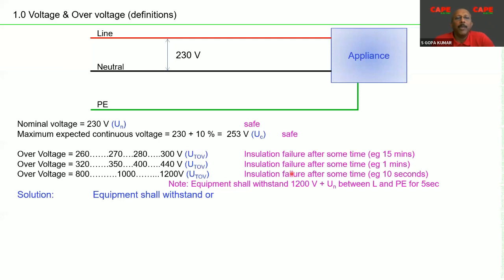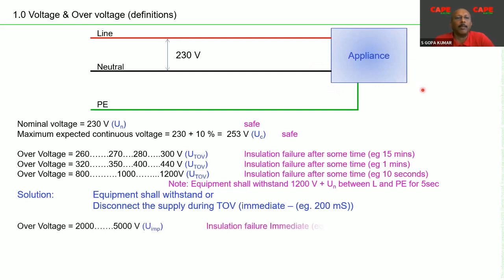Now here, we have two solutions to protect the equipment. The first solution is, probably the equipment is able to withstand that particular voltage. Instead of 10 seconds for 1200 volt, let's say it can withstand 1200 volt continuously, probably a special device. So this is one technique which can be applied to protect the appliance. The second technique which can be applied is, you disconnect the supply. In case of any temporary overvoltage, let's say for more than 200 milliseconds, you disconnect the supply. So the two techniques are: one, the equipment can withstand these high voltages; number two, if the equipment cannot withstand, you disconnect the supply.